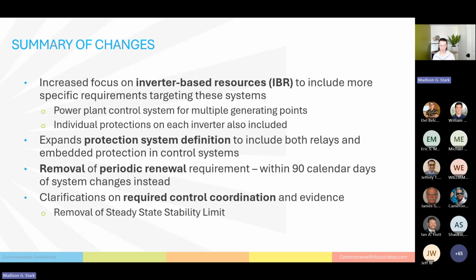It also, and this is a big one, is proposed to take out the periodic renewal requirement. So basically, if you don't change anything, you don't have to redo PRC 19 coordination. That 5-year requirement goes away, and it basically just turns into 90 calendar days after any system changes. So if you have a generator that's humming and you're coordinated and everything's good, great. Don't have to think about it. But if you change anything, you still have to think about it and do that updated coordination.